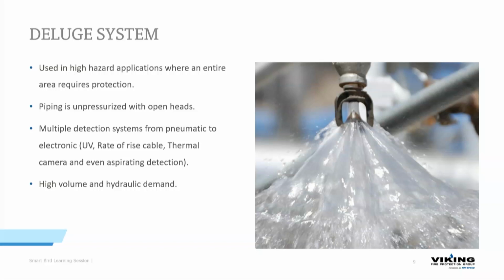Very high volume and very high hydraulic demand. Calculation of a deluge system, every single head is flowing at the full rate. So we don't have just a small area that we are flowing on our system. Every single head in that system is flowing at full flow.